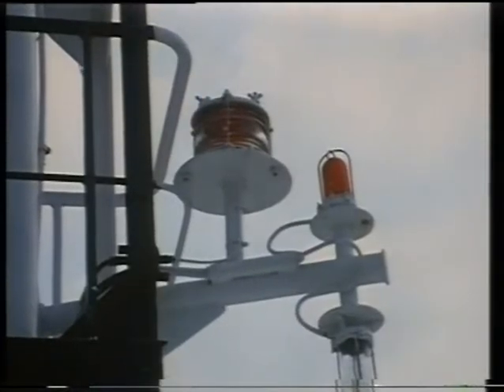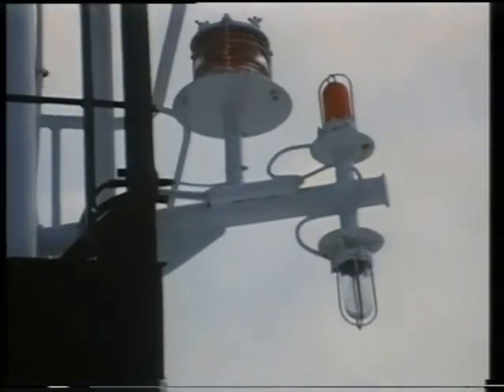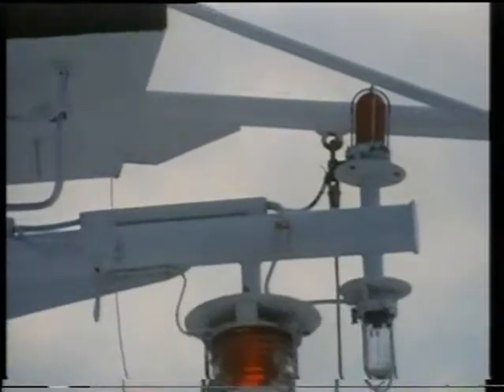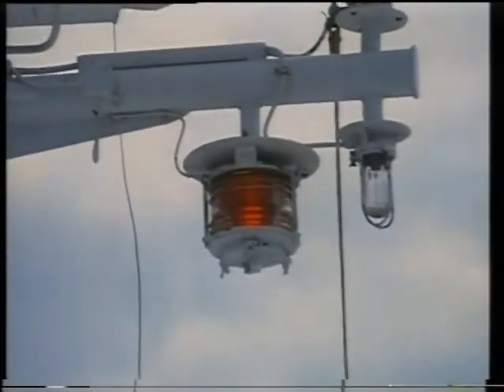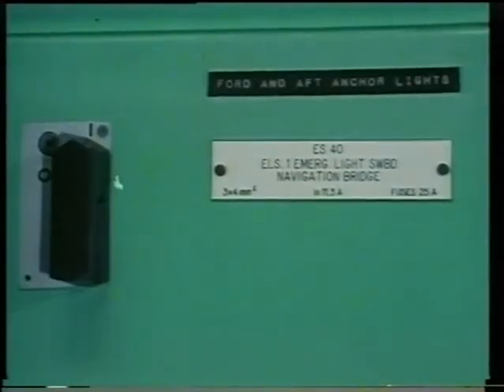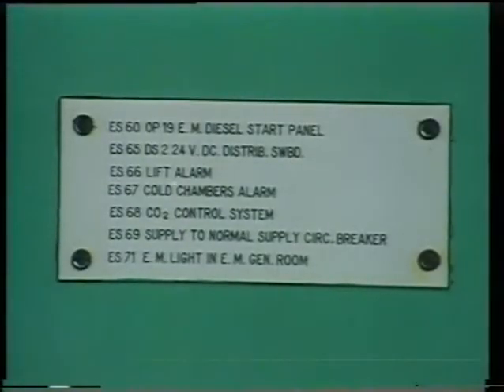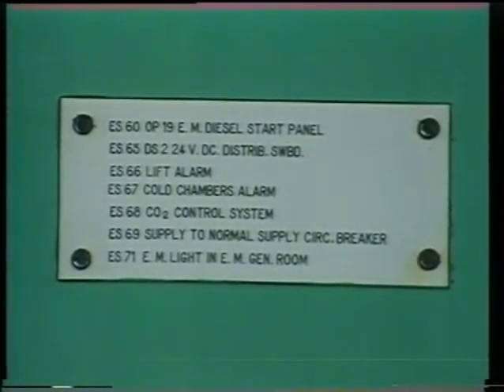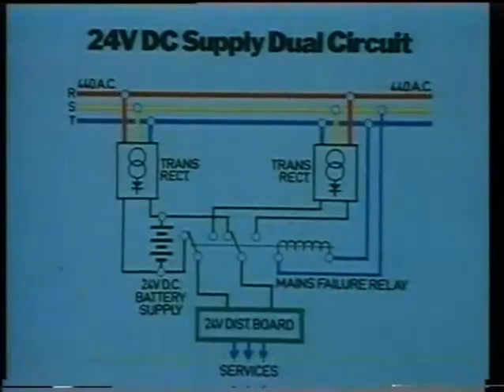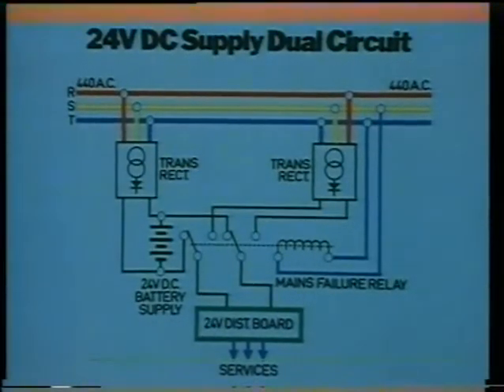the not under command signal lights, certain navigation aids, and the communication and alarm systems on board ship, in parallel with the emergency batteries. On a separate feeder circuit, a battery charger keeps the emergency batteries on charge during normal conditions.